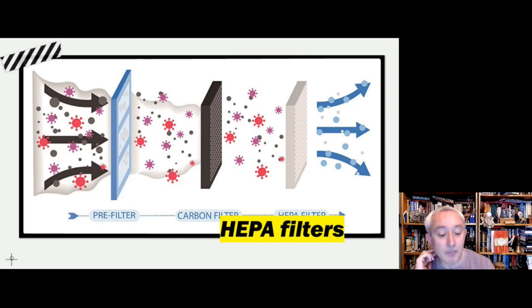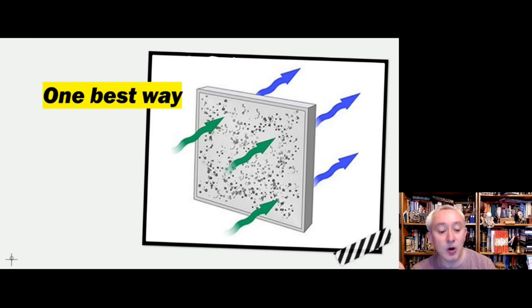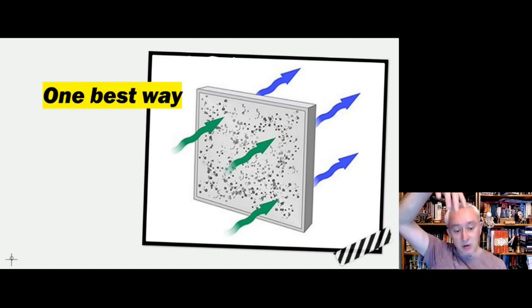Okay, so with the unidirectional airflow concept, we're ensuring that air flows only in one direction, the one best way, someone might say. And this lessens the possibility of particles being misdirected and landing on product contact surfaces or even inside vials.